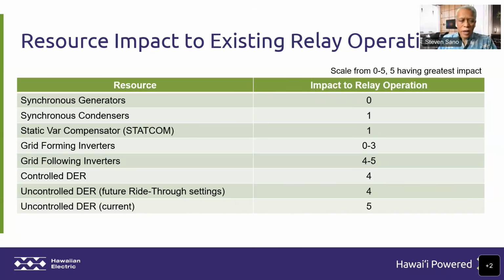The ride-through settings that are sort of evolving are giving us a better confidence in the protection system performance in certain situations, both at local and system levels. So that's up at a 4. Uncontrolled DER, which is sort of our default current environment, just because of when all of our DER went in on our distribution circuits. Uncontrolled, we have no visibility on it. It's at a 5.